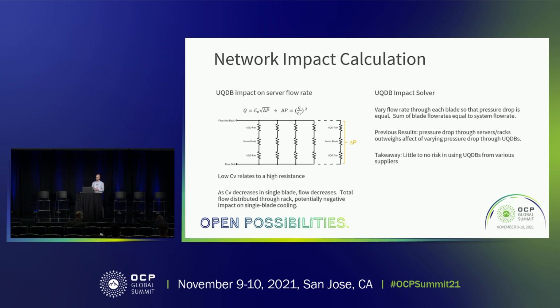So the takeaway there is, these truly are universal. We're seeing that even with no max CV value specified, as long as they meet that minimum requirement, they will work. As long as they work universally, they'll work supplier A to B. There should be no issue diversifying the supply chain and using these standardized connectors from any company.